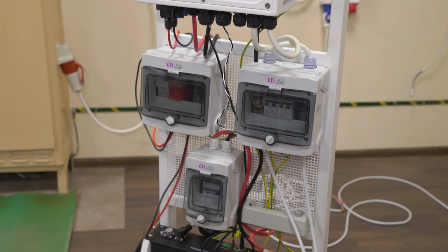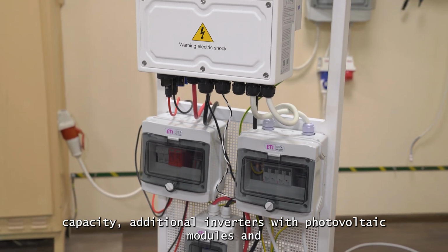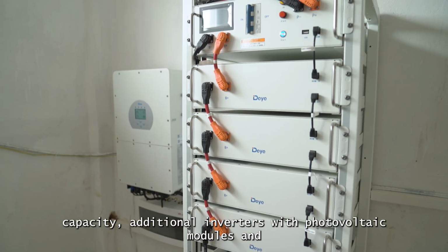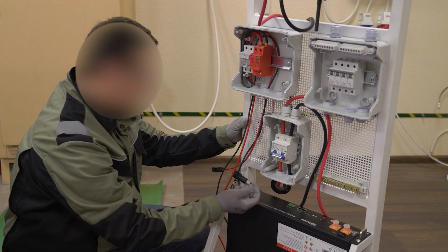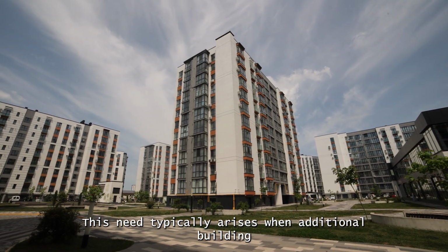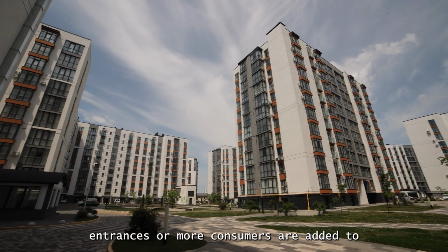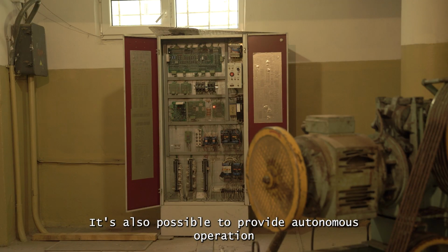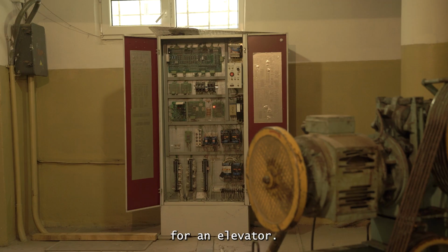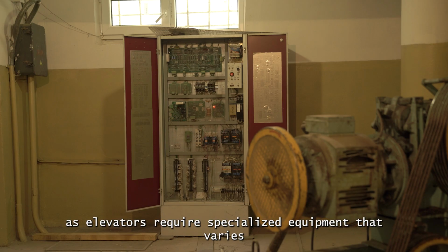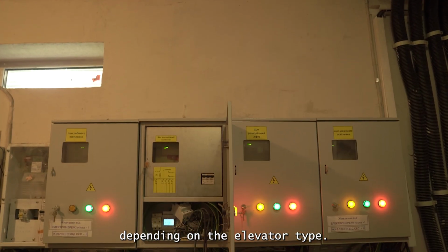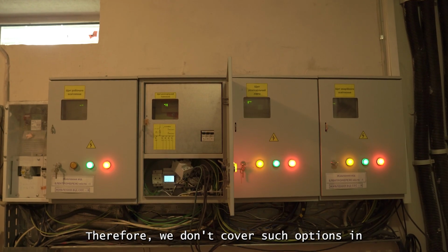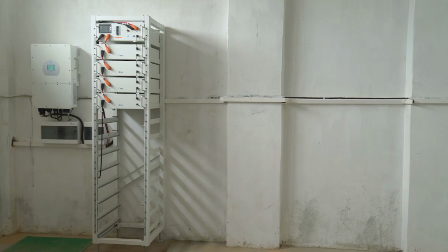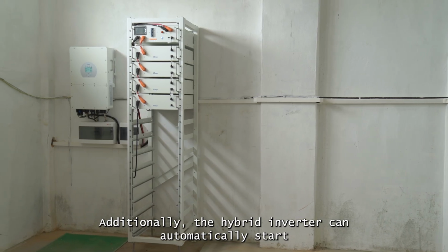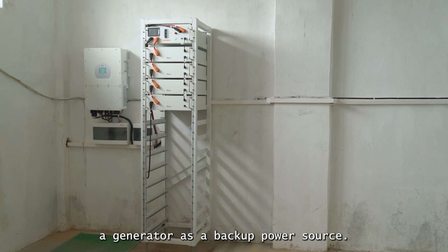Our system is modular. If there's a need to increase power capacity, additional inverters with photovoltaic modules and battery storage can be connected. This need typically arises when additional building entrances or more consumers are added to the system. It's also possible to provide autonomous operation for an elevator. However, this is a very specific setup, as elevators require specialized equipment that varies depending on the elevator type. Therefore, we don't cover such options in this instruction.